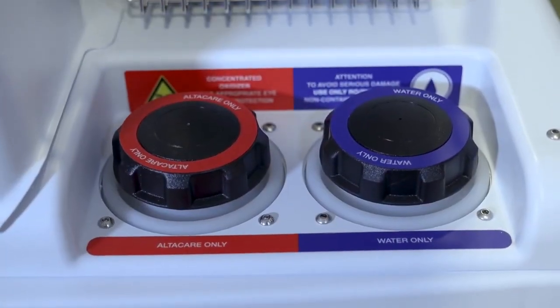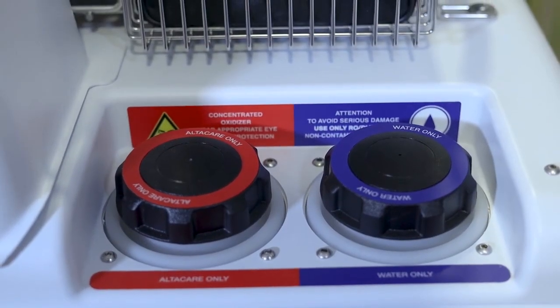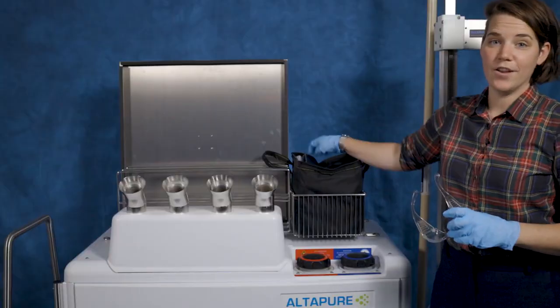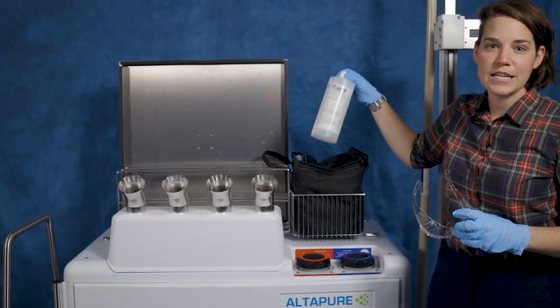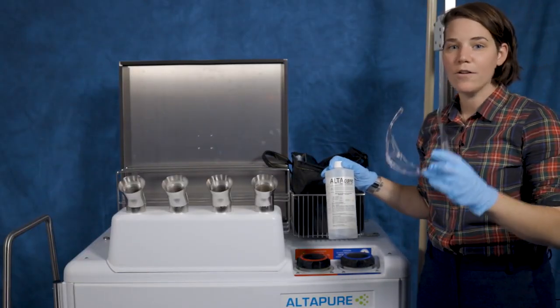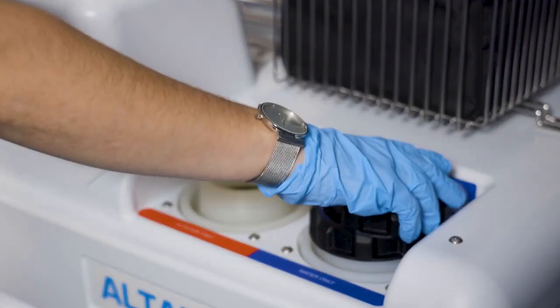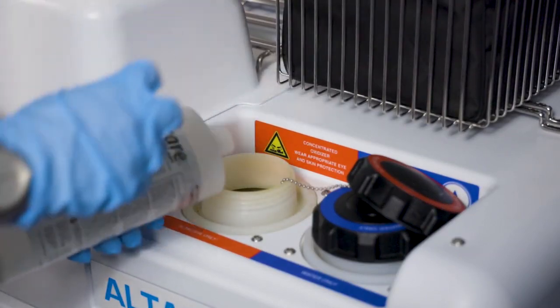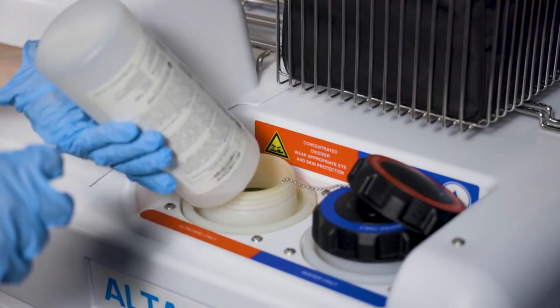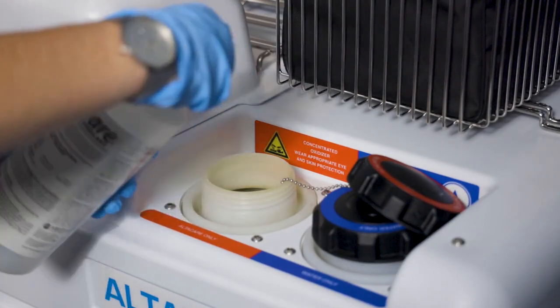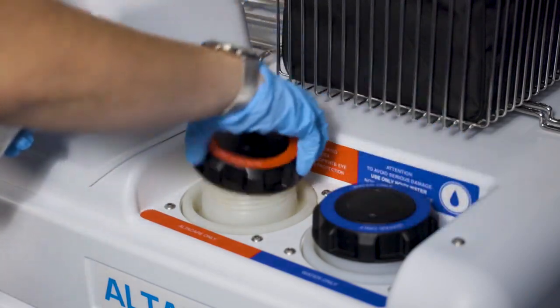Before bringing the machine into a room, verify the fluid levels and fill if needed. When handling the Altacare, it's important to wear personal protective equipment, or PPE. Goggles and gloves are recommended. Remember, RO/DI water only. Any particles in the water will end up on room surfaces. For the concentrate, only fill if the level is below 20%, so you can empty a full bottle of Altacare into the reservoir. The bar will change to yellow when it's below 20%.